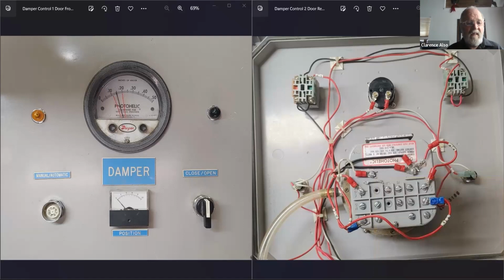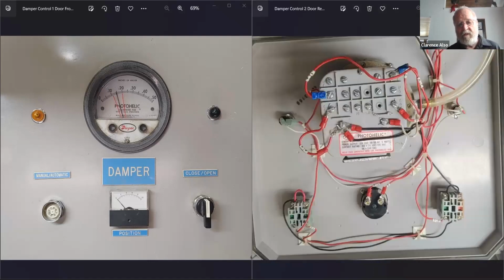Then we've got these lights here. This one comes on whenever we ask this thing to close - this light comes on when the close windings come on. You go to open, this green light comes on. So that's how a damper control works, moving that damper.